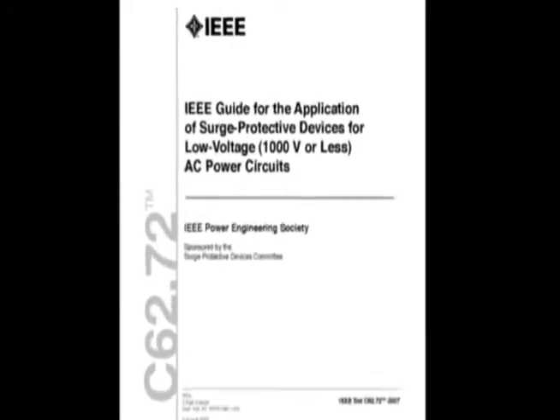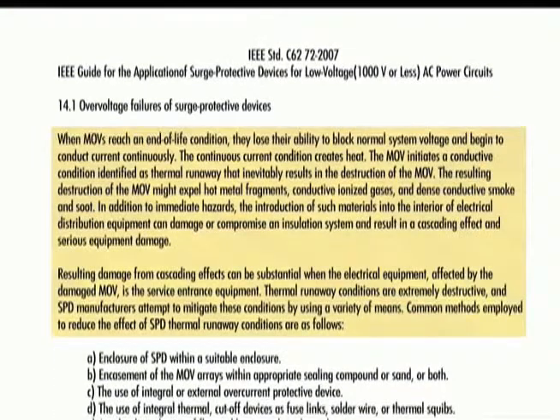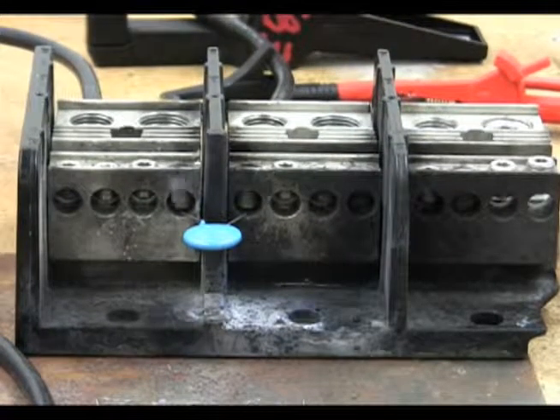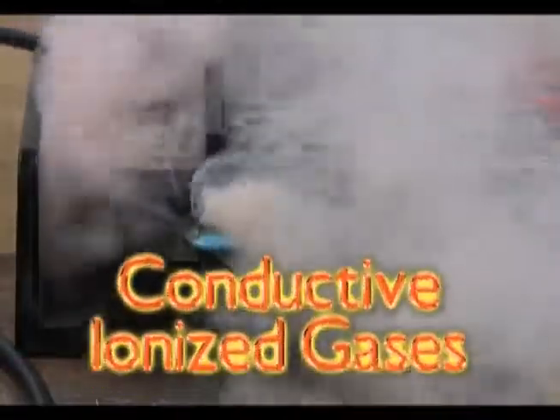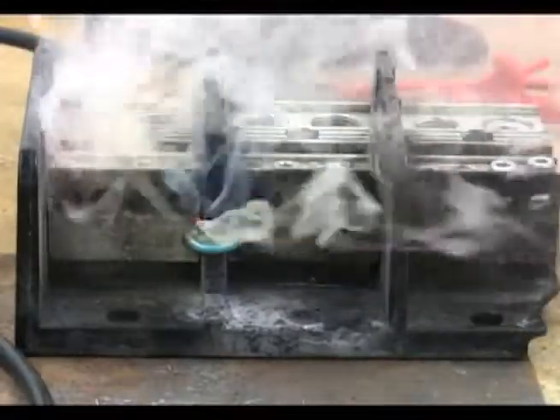However, even metal oxide varistors can fail. IEEE standard C62.72, the guide for the application of surge protective devices for low voltage 1000 volts or less power circuits, warns about the over-voltage failures of surge protective devices. When MOVs reach an end-of-life condition they lose their ability to block normal system voltage and begin to conduct current continuously. The continuous current condition creates heat, and the MOV initiates thermal runaway that inevitably results in destruction of the MOV, expelling hot metal fragments, conductive ionized gases, and dense conductive smoke or soot — potentially damaging or compromising the insulation system of connected electrical distribution equipment.